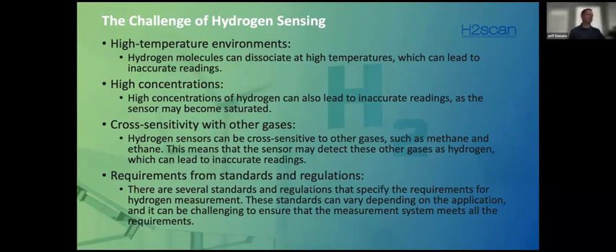Any kind of high concentrations can lead to inaccurate readings. Fortunately for batteries, like we said, it's a very slow build, so accuracy typically is not that much of an issue for the battery applications. But cross sensitivity with other gases can be an issue.